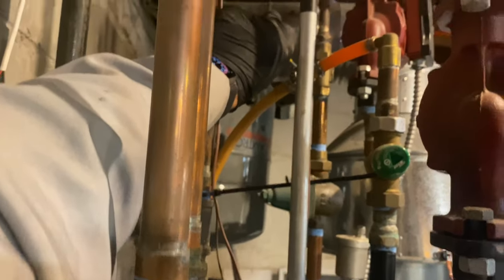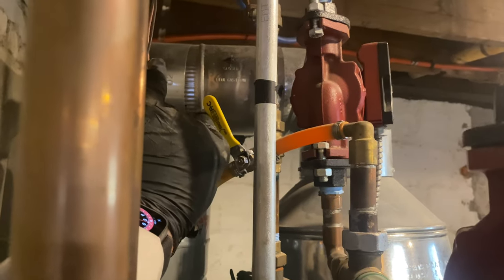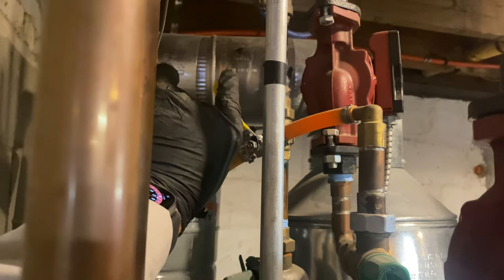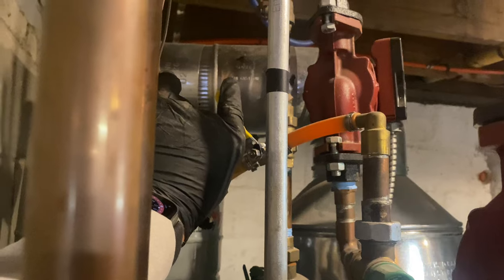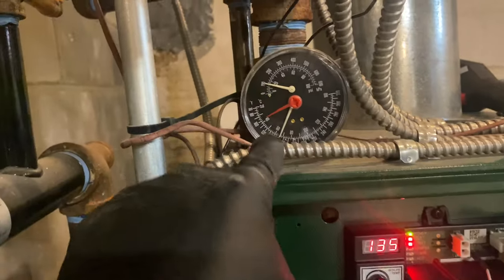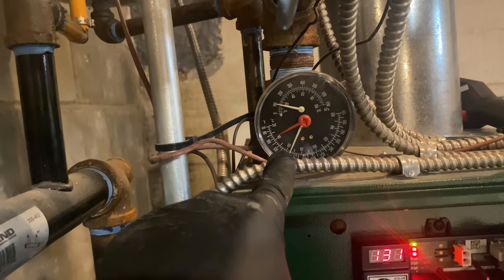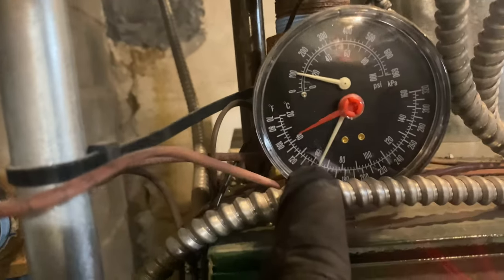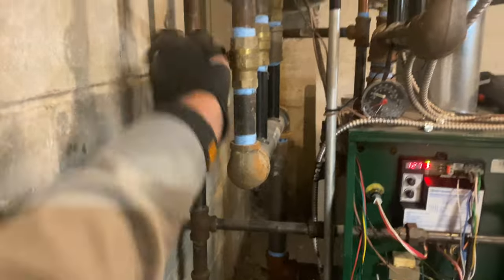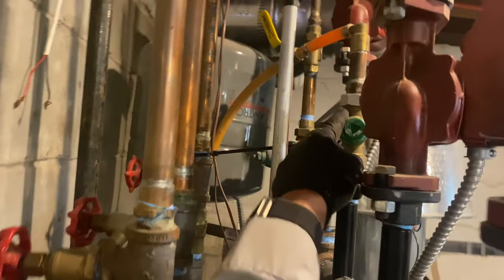Zone one isn't on, and I don't know why this is closed. It should be open, but yeah, zone one isn't on. This was closed before, right? I didn't touch this. Why do they have that closed? I don't know, interesting. See, we're dropping like crazy, look at our temperature, 150-ish there and dropping, see that? Yeah, I said the valve was closed before. Why this valve is closed at this mixing valve, I don't know, but that's the way it was, and that's for another day.